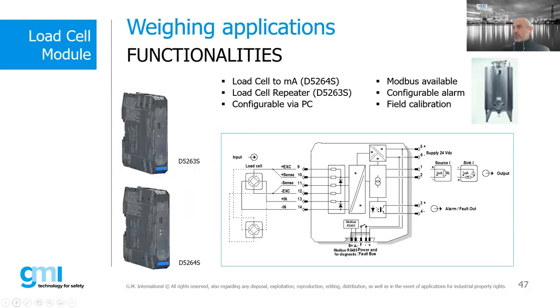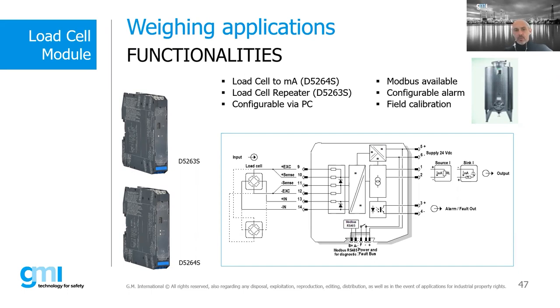We also have solutions for load cells, strain gauges, and weighing applications, where you can convert the load cell signal or strain gauge signal into 4 to 20 mA, or repeat the load cell signal to another load cell input. This is analogous to the temperature situation — some PLC/DCS cards have load cell inputs directly, but if your application requires a hazardous area connection, you need this type of isolator topology. Other features like Modbus and alarms are available on these models.